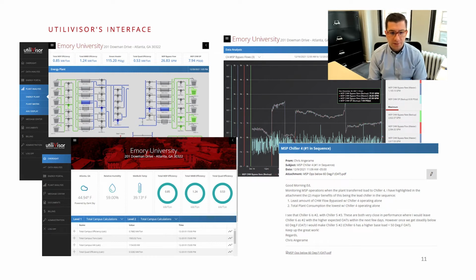Specifically, if I'm looking at a chiller, all the data I'm getting from the panel - power input, data from the flow meter, temperature differentials, refrigerant control - that's all being analyzed by our team, normalizing for what time of the year it is and whether the machine is part loaded. And is it meeting the criteria that the manufacturer set? Can I also do a little bit better?